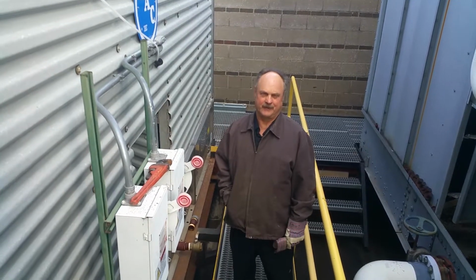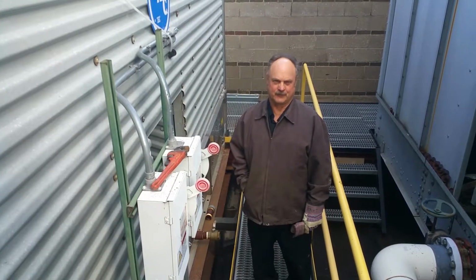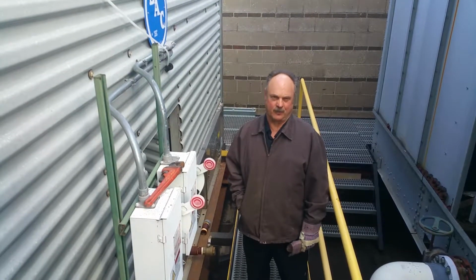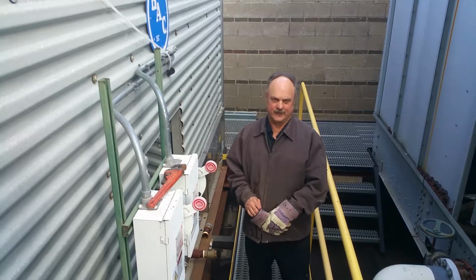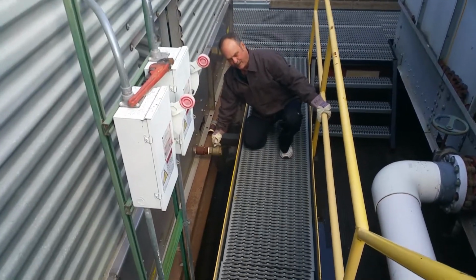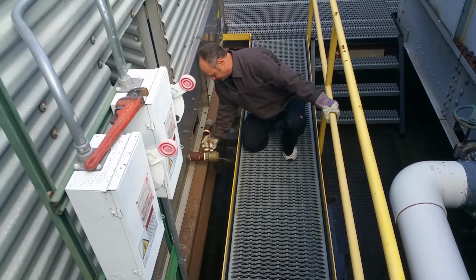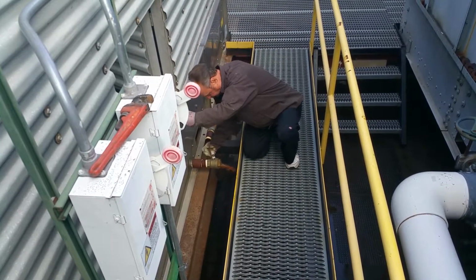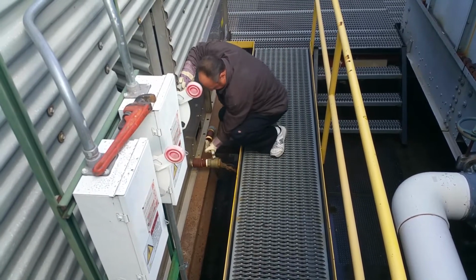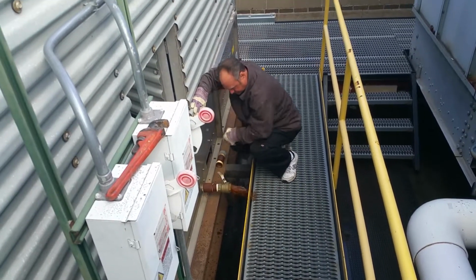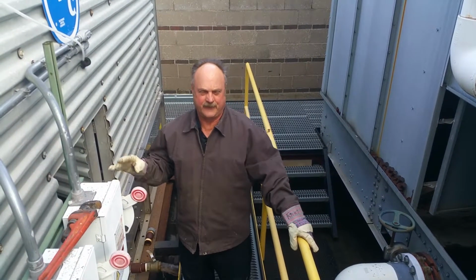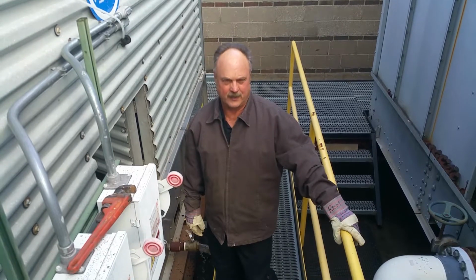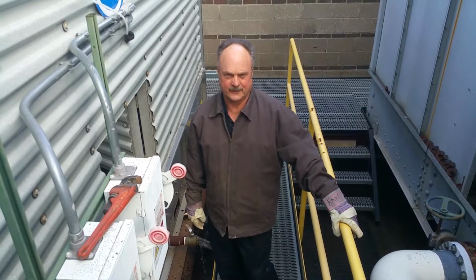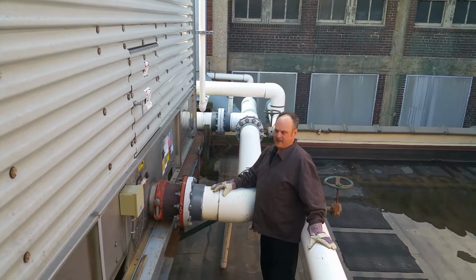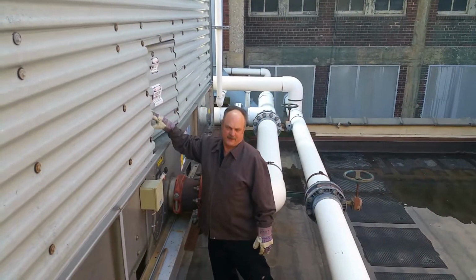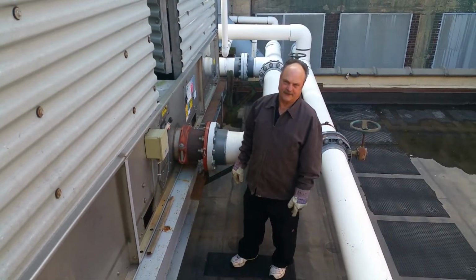We're up on the 6th floor on the north side of the building. What we're doing up here is opening the drain valves to drain the cooling tower. It takes about an hour to drain it totally. So that's what we're doing up here on top of the cooling tower. So what we're doing now is just opening the valve to drain the cooling tower. On the other side of the cooling tower, we have another drain valve on the west side, and we're going to go over there and open that valve, start draining on that side of the tower. On the west side of the cooling tower, we're going to open the valve over here and drain this side of the tower, just like we did on the east side.